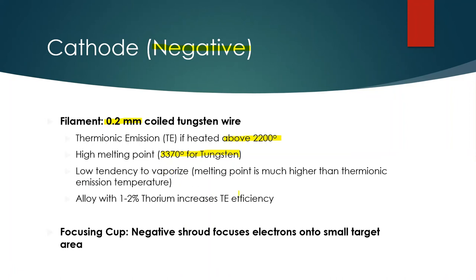We can heat the filaments high enough to cause the electrons to boil off away from the cathode filament. Some boil off while others cool down in a cyclical process, creating a cloud — a space charge — of electrons around the coiled tungsten wire. The coiled tungsten wire has a low tendency to vaporize because its melting point exceeds the thermionic emission temperature. In some cases, filaments are mixed with one to two percent thorium, which increases thermionic emission efficiency. The focusing cup, usually made of nickel, has a strong negative charge that focuses the electrons into a small target area.